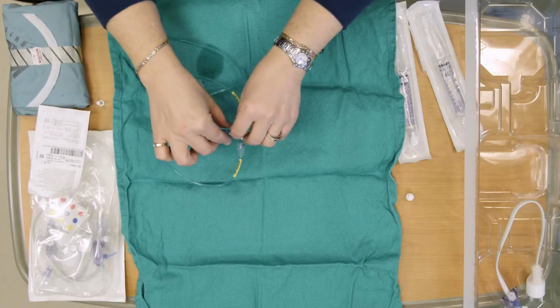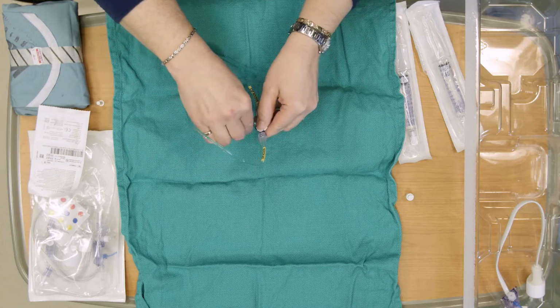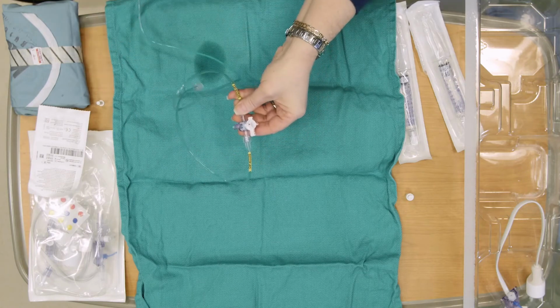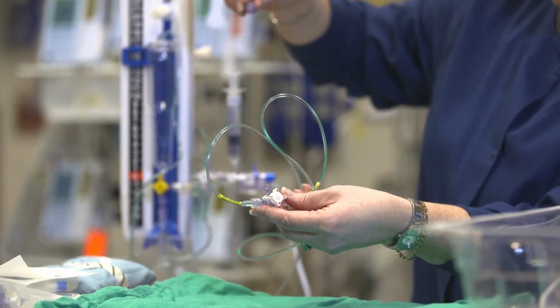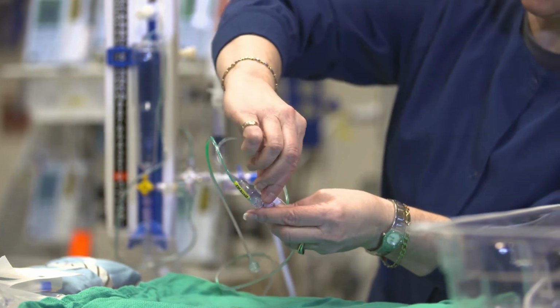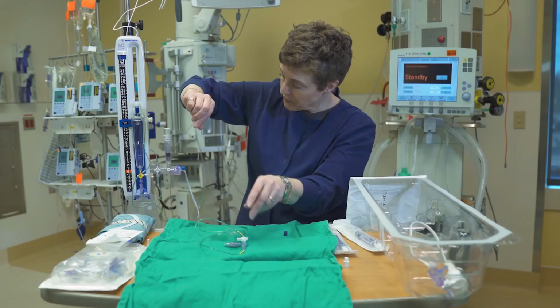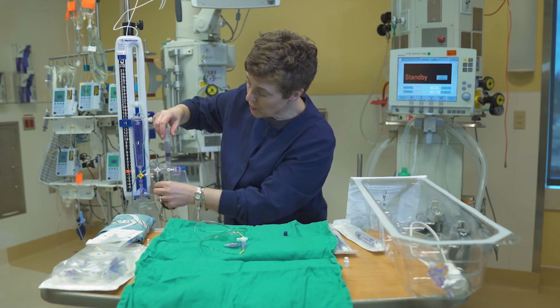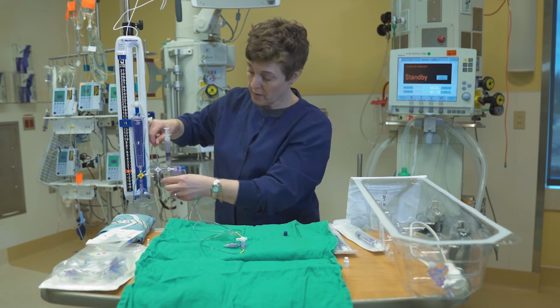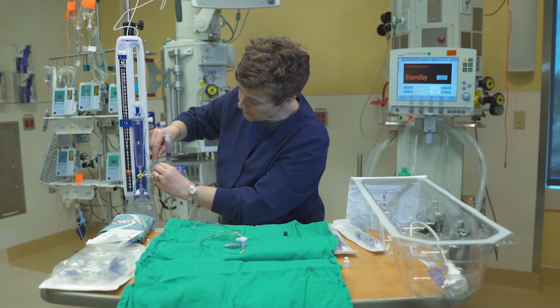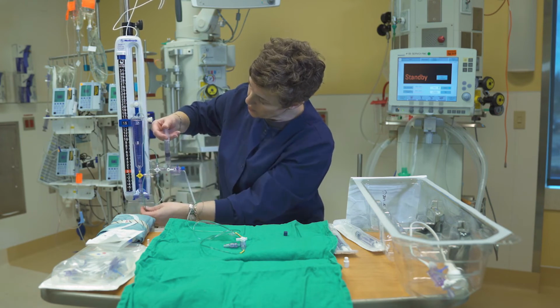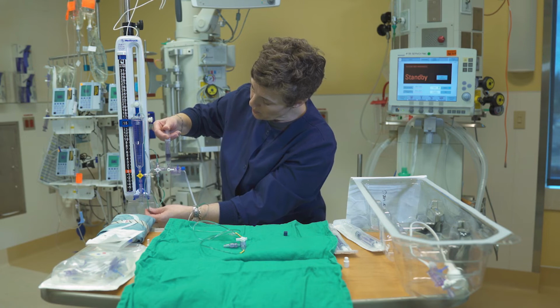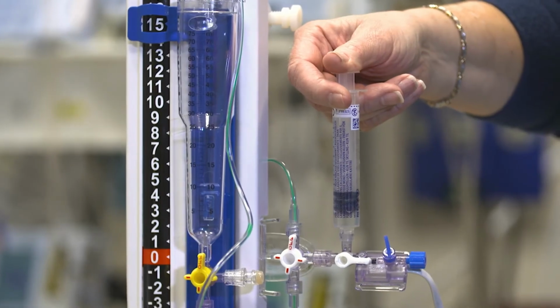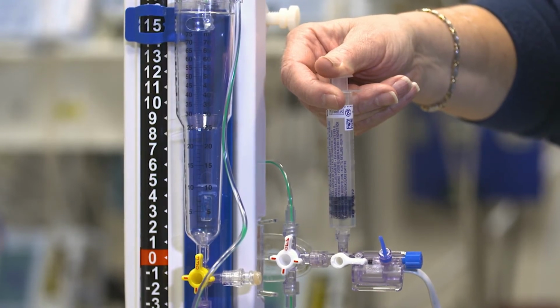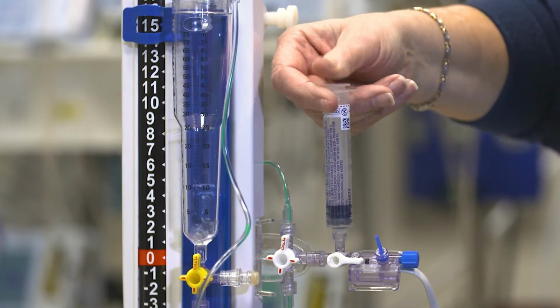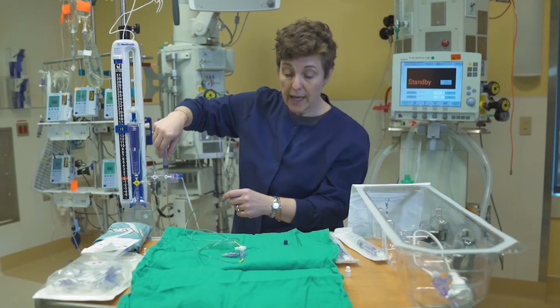So the last piece before I finish with this end is I'm going to turn the stopcock off to the end. I'm going to open this port, and I'm going to flush this port. Okay. So that port's filled. Replace the stopcock. Turn this back off again. I'm going to backfill the system the other way. So I now need to turn the stopcock off to the patient end, which is where we were before. And then you'll see the initial drop. And I'm just going to go, because this is where we measure our drainage. So I just want to see a couple of drops come down. And a little bit more than I wanted, but that's now finished.